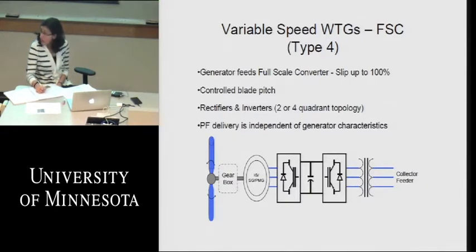The reason we do this is that now we can control slip all the way to 100%. We can have total control of the slip characteristics of the mechanical energy coming in to the torque driving the generator, but we can completely divorce that from the electrical output of the generator to the grid. And in doing so, it gives us tremendous flexibility with this type of design. Now if you see the generator design, we can use an induction generator or a synchronous generator or a variation of a synchronous generator, a permanent magnet generator, because we're not controlling the excitation anymore. Or we might want to control the excitation, but we don't necessarily have to, because we can totally control the output of the generator through these power electronics and then out to the grid. Again, this may or may not have a gearbox. That's a different decision. That's a totally mechanical decision.